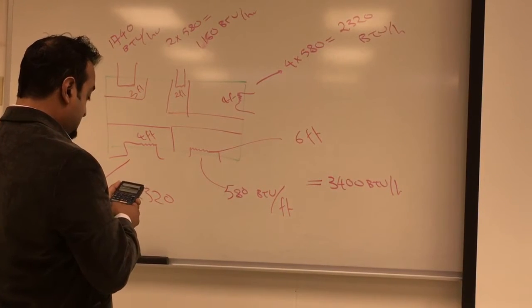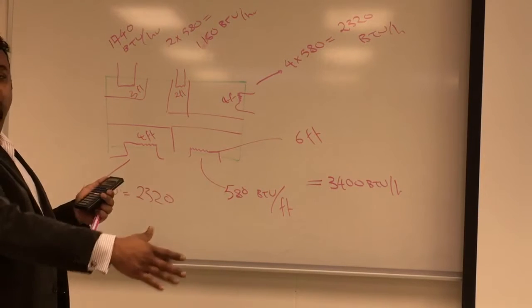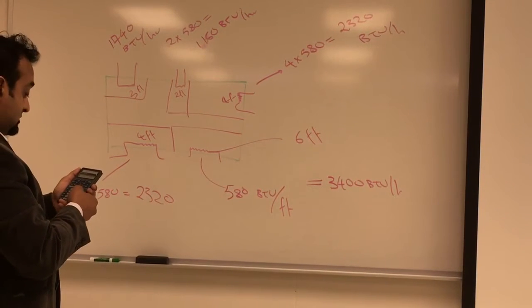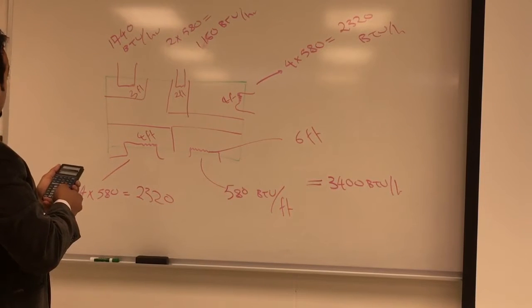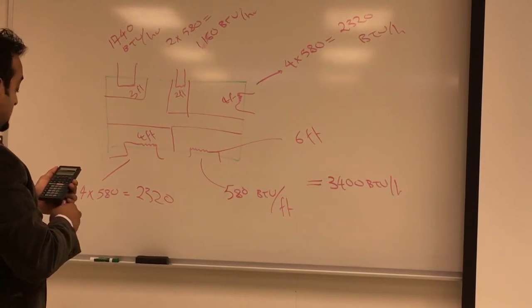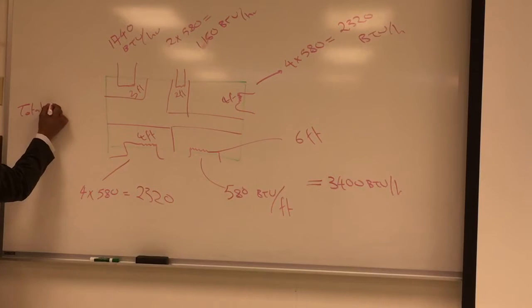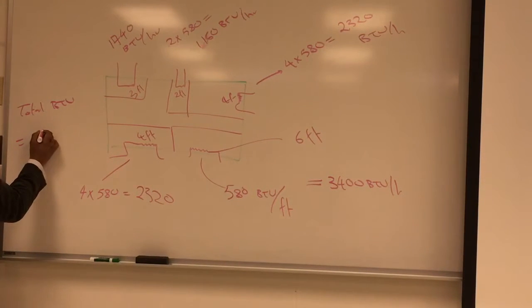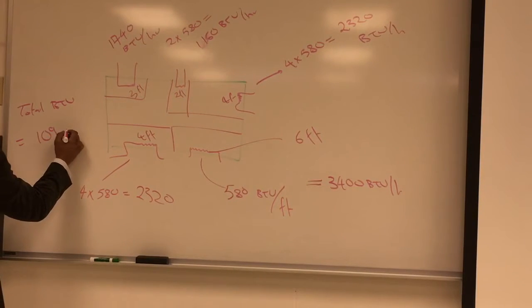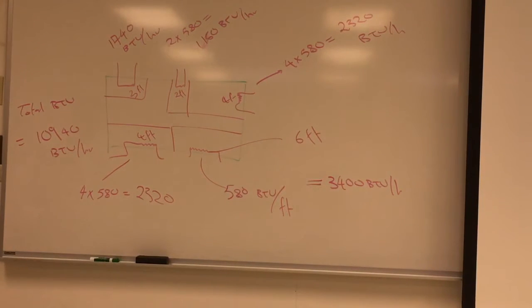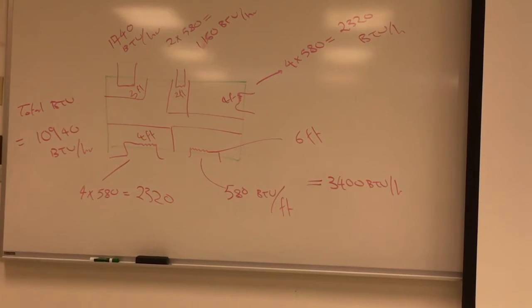The BTU per foot value—is it always 580? No, you get that from the different radiator specifications. So here I got 10,000 BTUs total. It's a very small unit according to the size. I'll add 15% for the losses, so that's multiplied by 1.15.